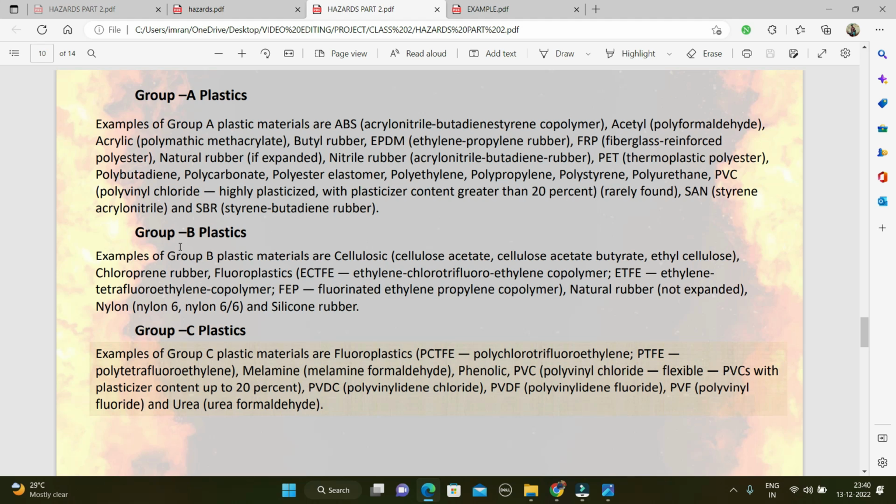Okay, why is it very important to select correctly? I already explained that if we select any wrong hazard or any wrong group, then the whole system will be changed. Before designing we have to select the hazards, and if we select the wrong hazards, then our K factor, design area, and number of sprinklers in the design area will all vary, all will be changed.